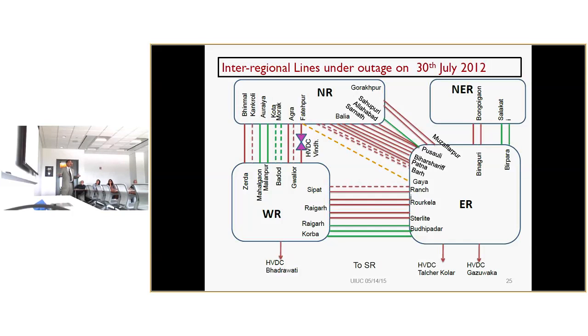Why were they saved? Frequency went as high as 51 hertz. I mean, 50 is the nominal frequency. They were fortunate. Some of the generators tripped. We don't know the reason actually, but they tripped. We could verify from the disturbance record, and also there were only six PMUs in northern region at that time and five PMUs in western region. Eastern has few PMUs. They were not working at that time. They had not been commissioned at that time. So that was the situation.